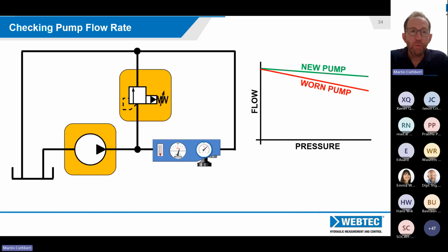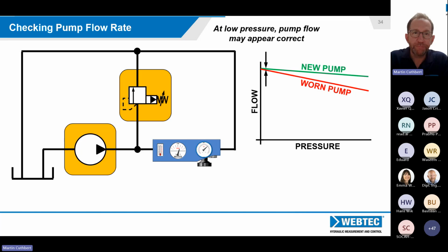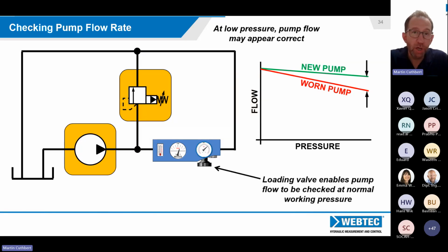So what we know about pumps is that if you were to test them at low pressure, as you can see from that graph at the top there, the pump flow may appear correct. And then with the help of the load valve, you can restrict the flow, the pressure will start to go up, and then you can see how the PQ curve develops, if you like. So what's the flow as the pressure is increased? And the aim being that you'll see the volumetric efficiency deteriorate if the pump is worn, or might deteriorate much more quickly than if it was a new pump.